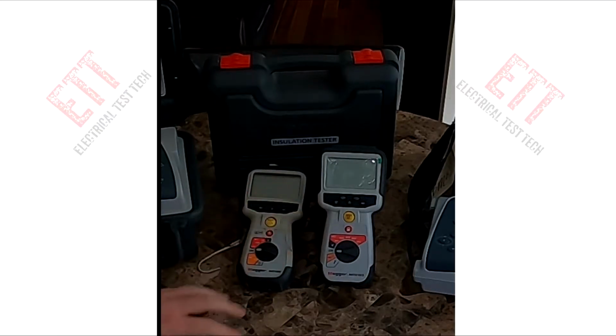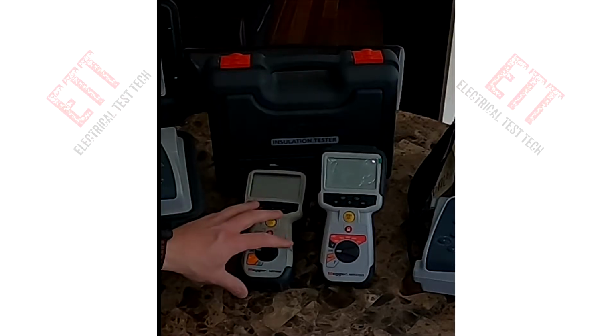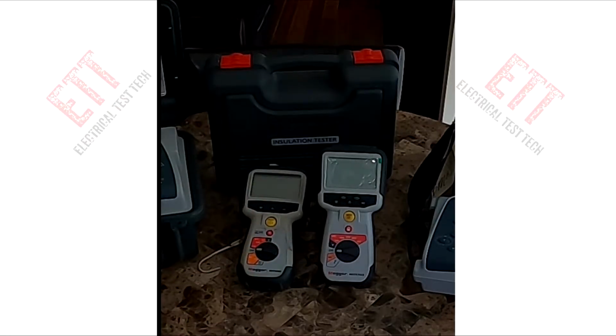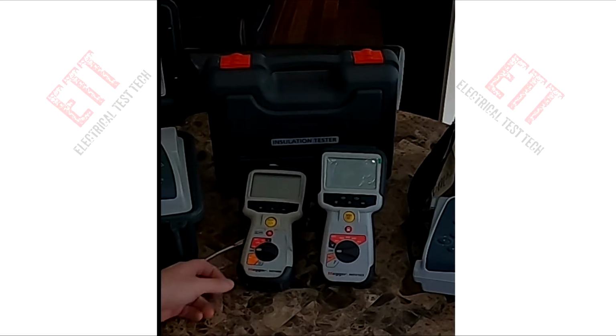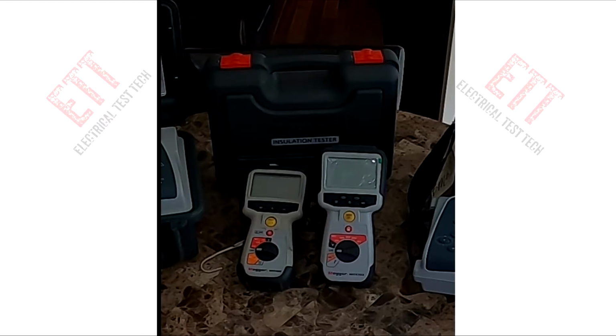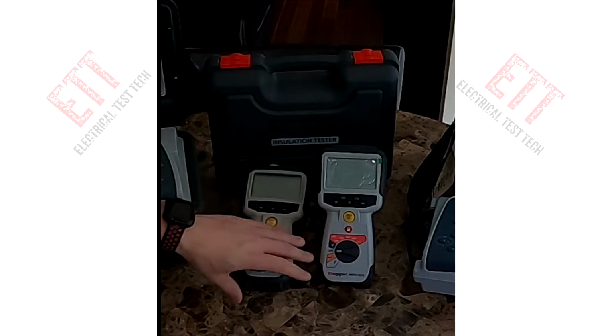These are an everyday carry item. They stay on the truck. For any test technician, this is a 100% must-have on any field service tech's truck. It's used on many different applications, any type of low voltage cables, switch gear, anything 600 volt and under. It can be used on higher class voltage stuff, but it's not for any type of acceptance test. You would typically use it just to see if something is clear. So typically 600 volt and below.